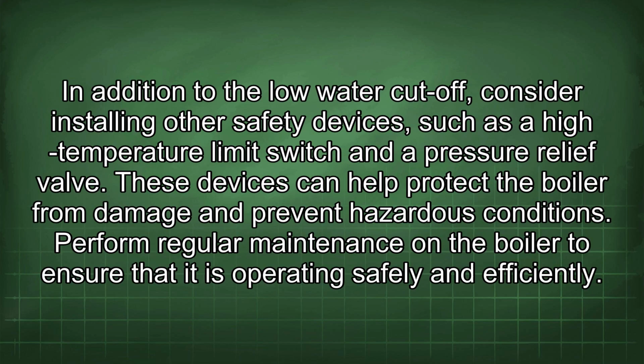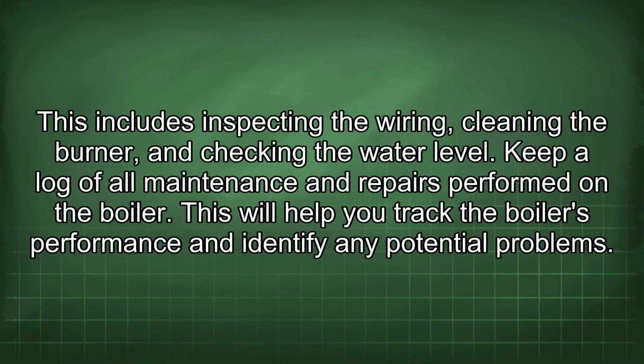In addition to the low water cutoff, consider installing other safety devices, such as a high temperature limit switch and a pressure relief valve. These devices can help protect the boiler from damage and prevent hazardous conditions. Perform regular maintenance on the boiler to ensure that it is operating safely and efficiently. This includes inspecting the wiring, cleaning the burner, and checking the water level. Keep a log of all maintenance and repairs performed on the boiler. This will help you track the boiler's performance and identify any potential problems.